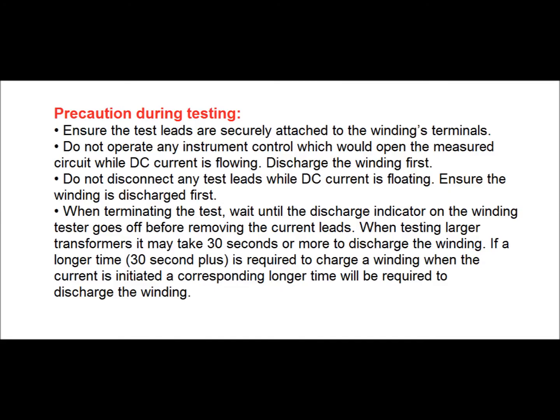During the DC resistance test, first we have to open all the jumpers to the HV and LV bushings, and also open the earth flat connected to the neutral if it is a Y connected transformer. We have to ensure the test leads are securely attached to the winding terminal. Do not operate any instrument control which would open the measuring circuit while DC current is flowing. Discharge the winding first.